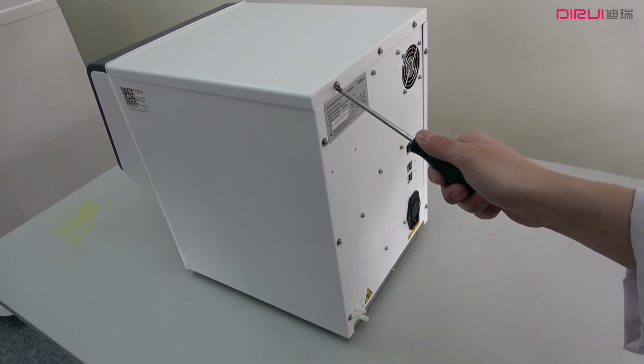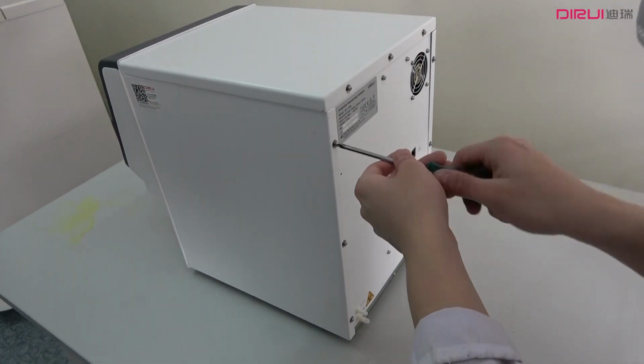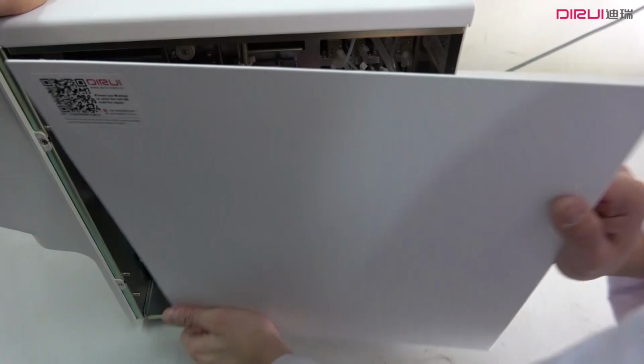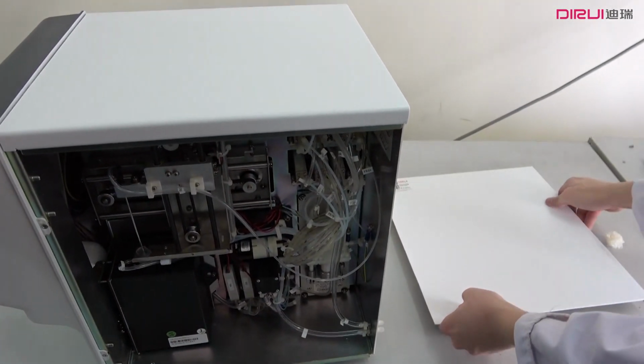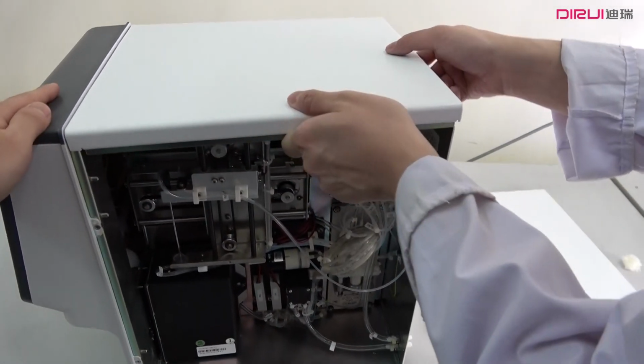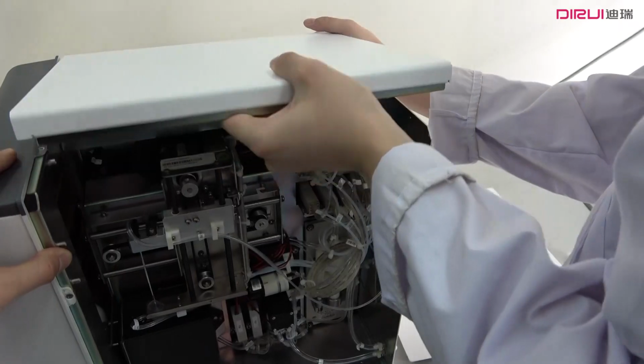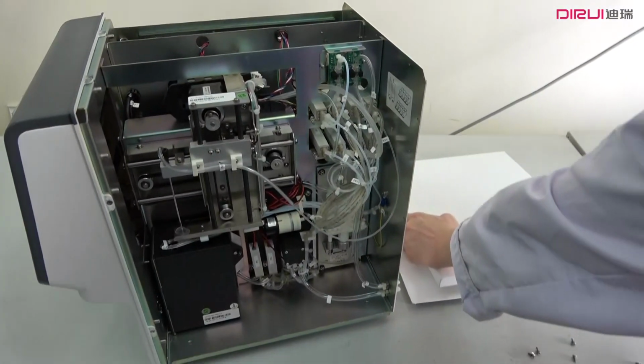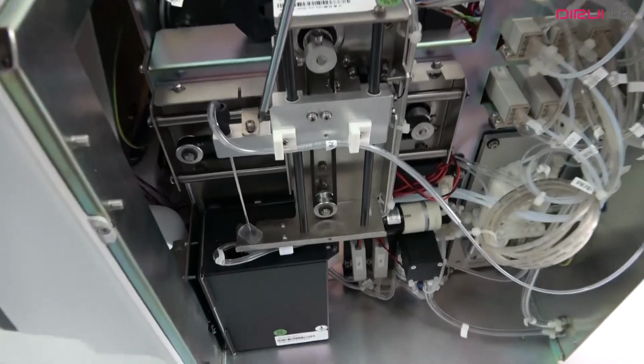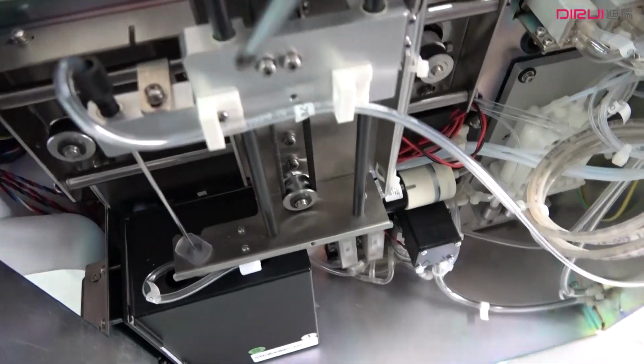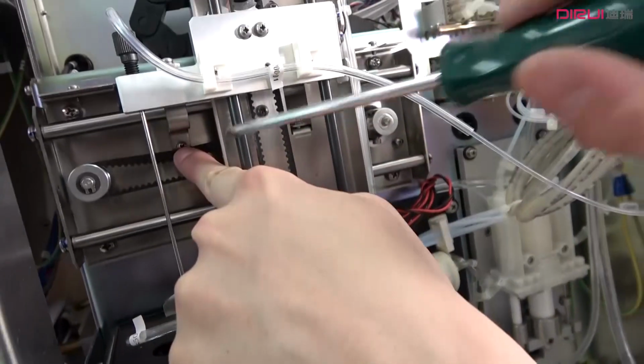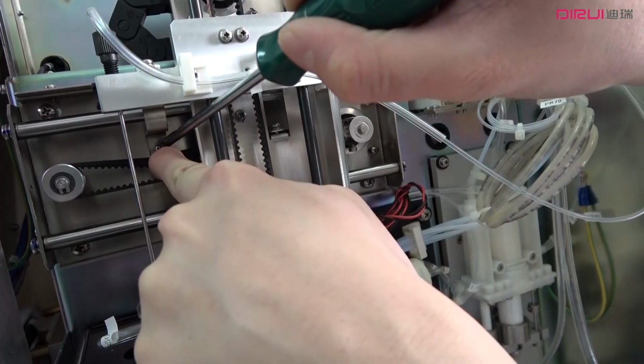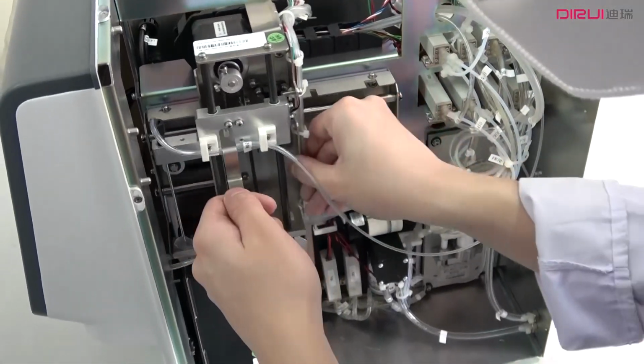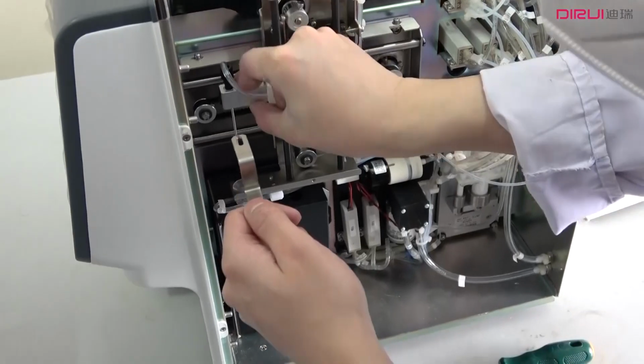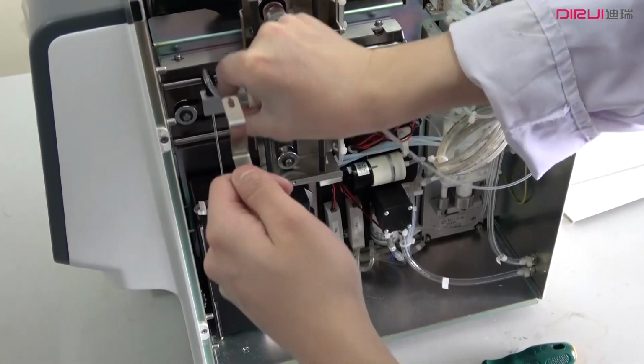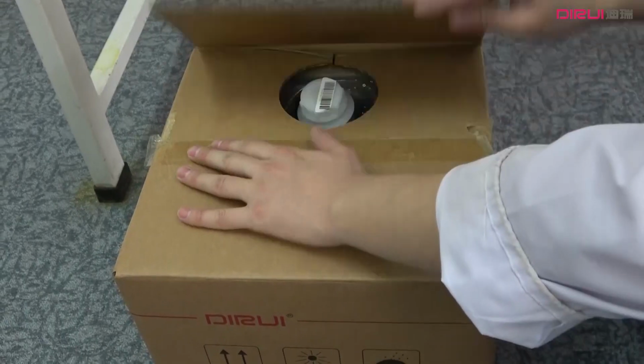Open up the screws of side and top cover. Remove the metal sheet covers from side and top of the instrument. There is a protective hook which holds the probe from moving. Please open up the two screws and remove this hook and carefully observe if the probe can move right, left and up, down freely. Open the diluent reagent box.